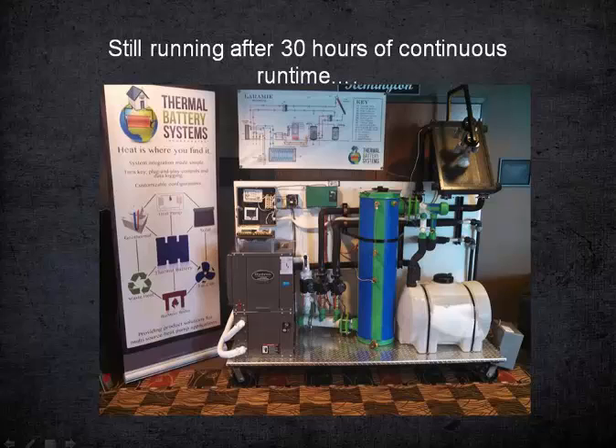Yeah. Aquatherm built that to our specs. It's a 12-inch Aquatherm climatherm pipe capped on the ends, and then I built the headers that came off the unions from that point to do what we wanted. This one was adapted a little differently than what we have normally done. If this is looked at as a straight drain back solar into that tank, it happens to be non-pressurized, although the way we configured it, it could be made for a pressurized or non-pressurized system. There's a gauge tube on there to see your water level, room for relief valves and fill ports, pressure gauges, and whatever if it is a pressurized system, and a thermal well to tie into our control system for the thermal battery system.